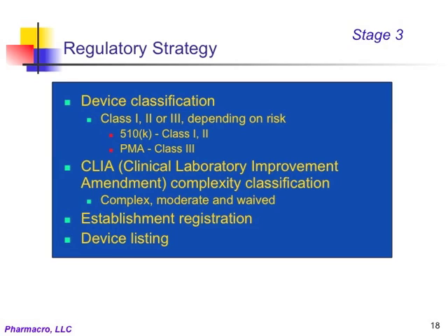This involves first classifying the device in accordance with regulatory guidance as Class 1, 2, or 3, depending on the risk associated with the use of the device. The device classification determines a regulatory approval path that will be necessary. Class 1 and Class 2 devices require a so-called 510K clearance path, and the higher risk Class 3 devices require a so-called pre-market approval or PMA path. The regulations define the requirements for approval along either one of these paths.